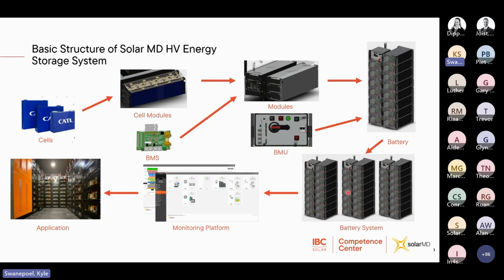They can then be connected in parallel, so that will give you your desired storage capacity. Just one thing to note with your HV solutions, the voltage obviously needs to be the same in order to connect in parallel. And then you've got the SolarMD monitoring platform, which we'll touch on a bit later. And then you can see here we have a solutions picture, which is taken from one of the HV sites here in Cape Town.